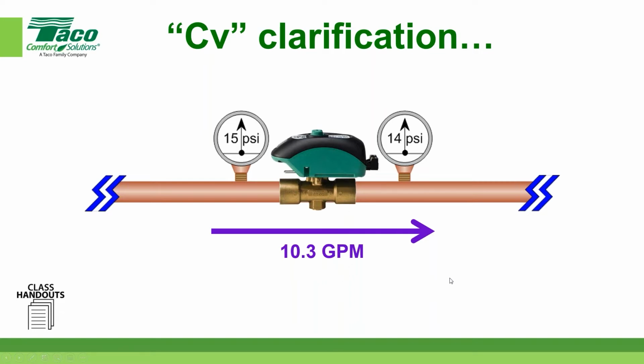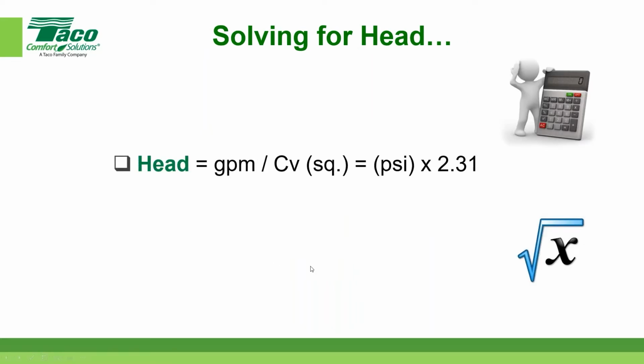Hopefully that helps explain it, and hopefully, instead of just throwing your arms up, that will help you understand, especially when we start building that into calculations. So when we solve for that, let's show you how this is used in a calculation. If we're solving for head, we do that by figuring out what GPM we're going to run through the device. Here's the device's listed CV, okay? And then we square that. That squaring gives us the PSI drop, and we convert that to feet of head.